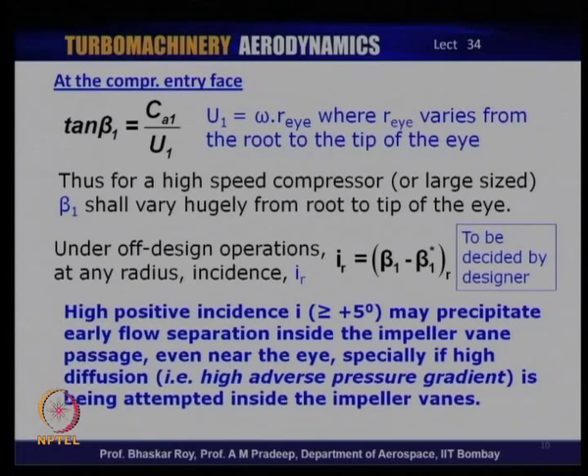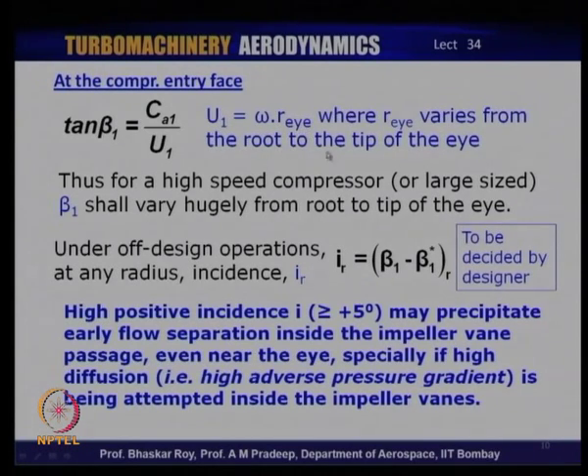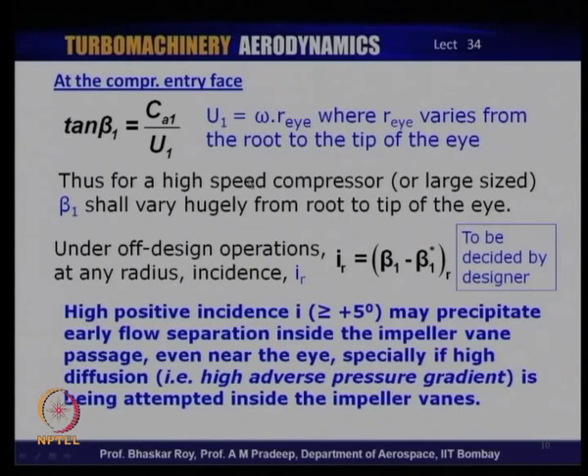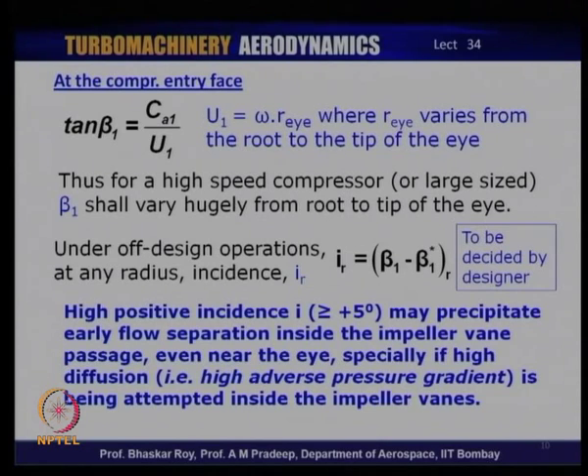Let us start at the beginning of the centrifugal compressor where you need to create the inlet flow and the inlet vane shape. The flow comes in with tan β₁ = Ca₁/U₁, where U₁ = ω·r of the eye — which varies from the root to the tip of the eye. So U₁ and β₁ both vary, and as a result you get a twisted inlet eye. The eye of the impeller is actually fairly highly twisted in a high-speed compressor or in a large industrial compressor, and this twist has to be factored into the vane shape — so the impeller entry is often a twisted vane.